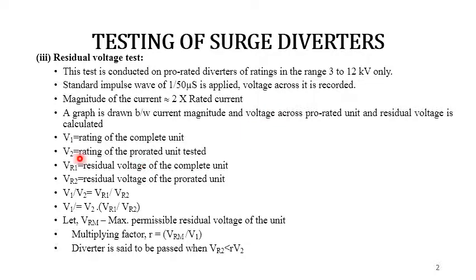These are some of the nomenclature which we are going to visit. V1 is the rating of the complete unit. V2 is the rating of the prorated unit under test. VR1 is the residual voltage of the complete unit. VR2 is the residual voltage of the prorated unit. It is assumed that V1 by V2 is equal to VR1 by VR2. Let Vrm be the maximum permissible residual voltage of the unit. Then the multiplying factor R is defined as the multiplying factor of the rating for the residual voltage, which mainly depends upon the value of V1, and the diverter is said to pass when VR2 is less than R times V2.